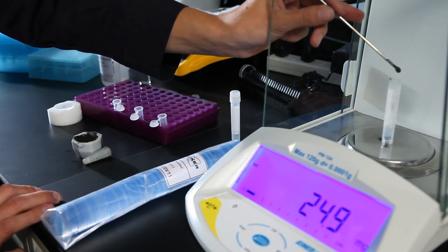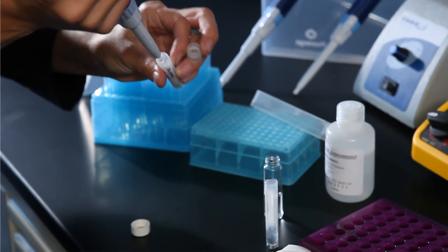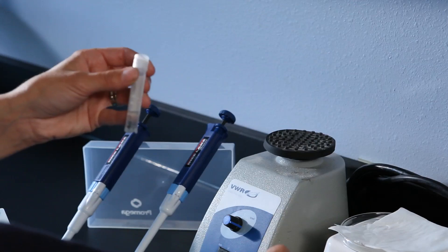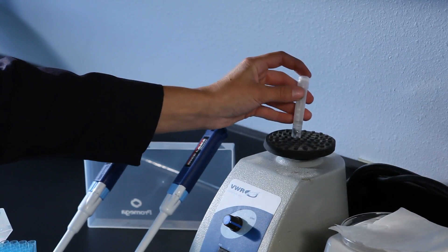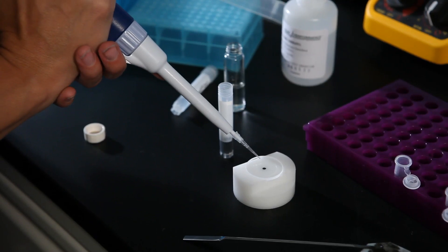A solid sample is prepared by first grinding it up into a particle size of under 50 microns. From there we use a common laboratory balance to weigh the sample. We then suspend that sample, which is very nice because we don't need to use those long acid digestions as you would with other equipment. We then add our internal standard, create our suspension, and pipette onto the disc.